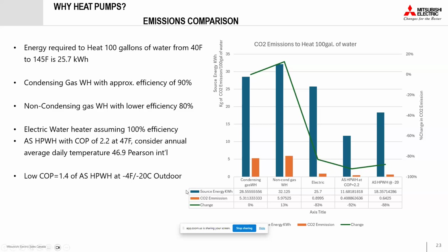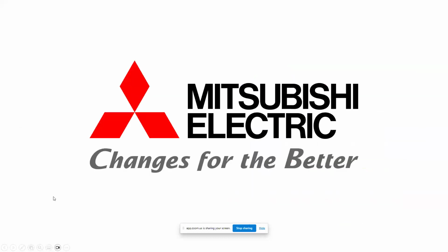In most of the period when you will be using those electric heat pumps, they'll be working at a higher efficiency of 2 or more, even up to 4. So on average, that will be much, much higher than 2.2. So you can expect that your energy consumption and your carbon emission will both be reduced by almost 50% or more. In some current studies, they find that especially where the older system was natural gas, it amounted to even 60 or 80% or more. So that's the end of my section, and I'll hand over to Tyler for the next portion.